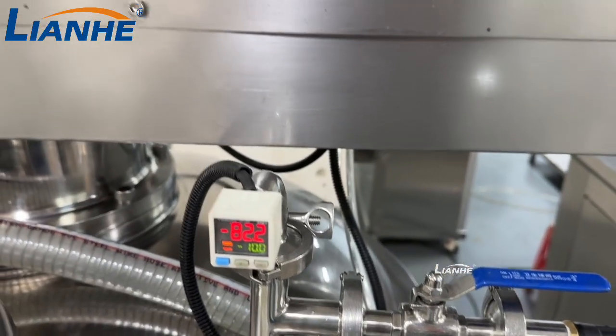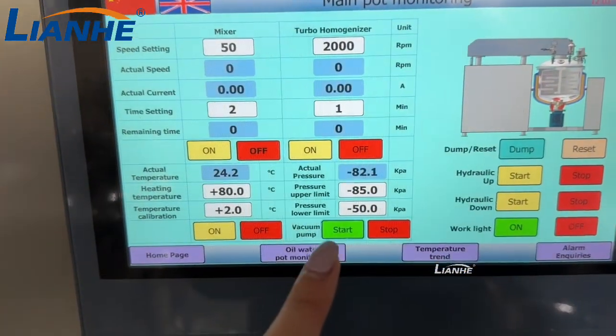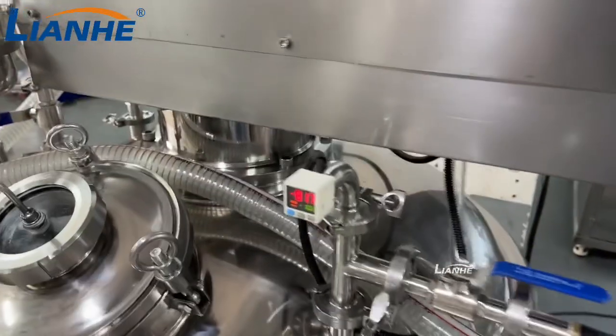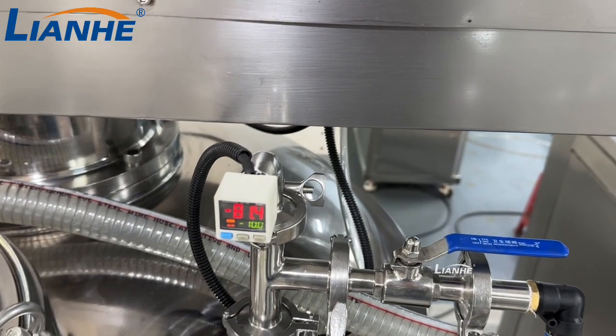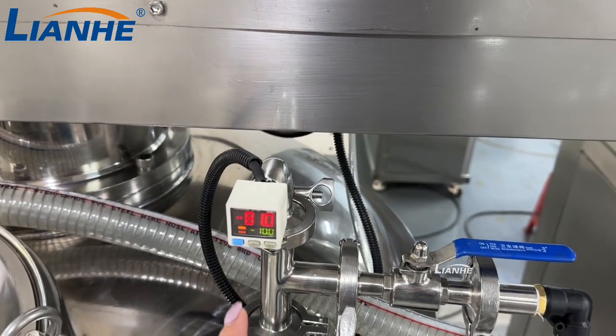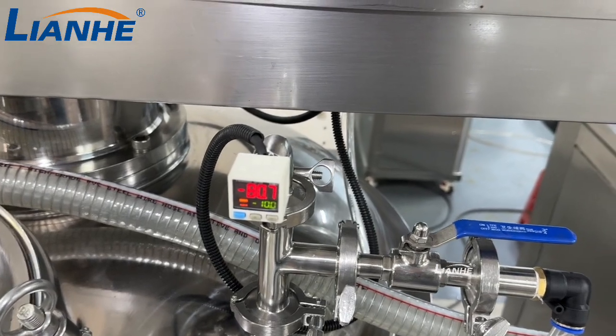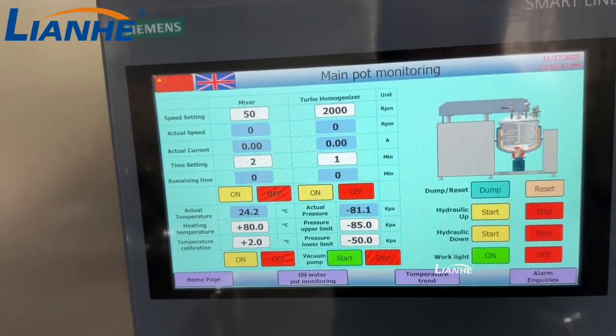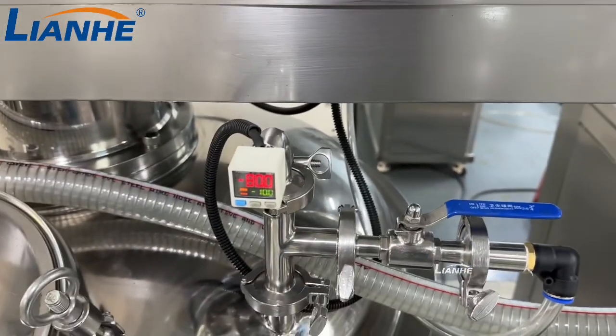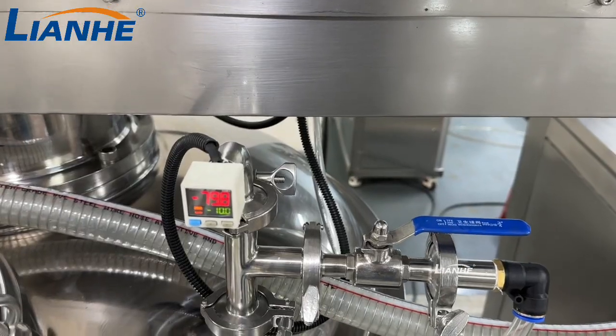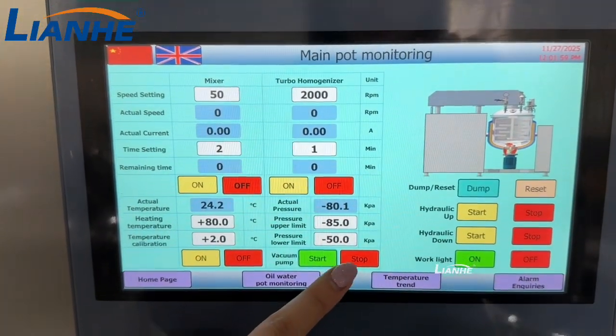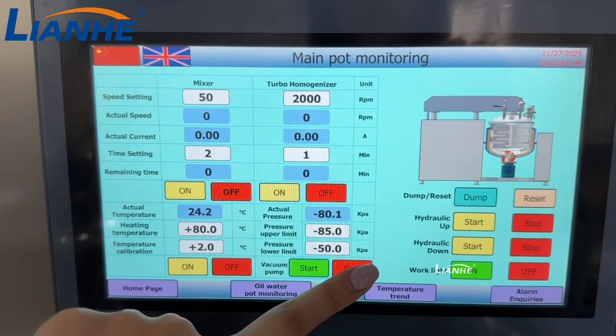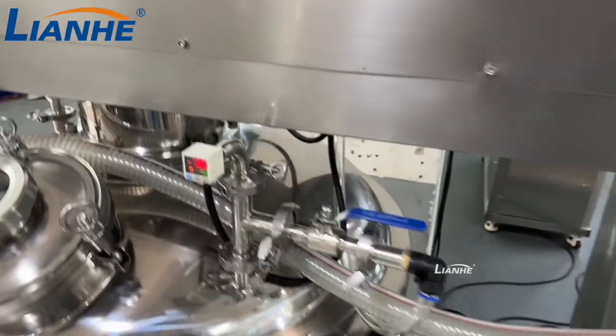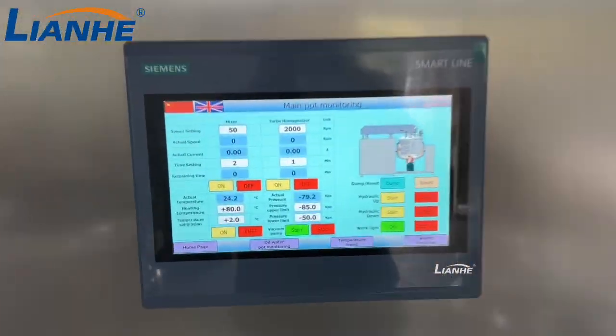You may check here. And then you can see you set the pressure low limit is -50 kPa. If this pressure is changing, and when this pressure is going down to -50 kPa, just like you set here, the vacuum function will start working again. You will check here. And then if you want to keep this maintained in the vacuum stage, you can just turn off the stop button here. And then the pressure you keep here, stop.